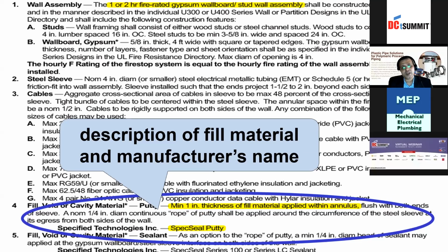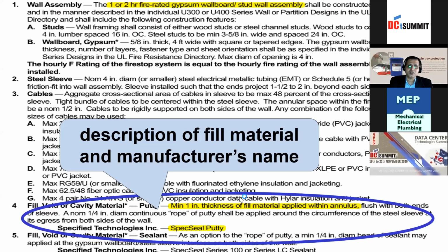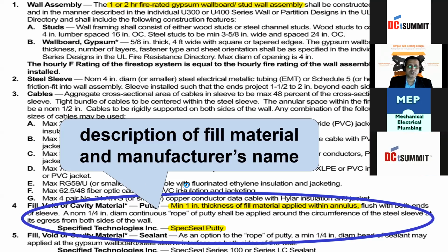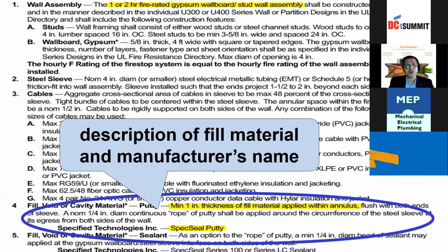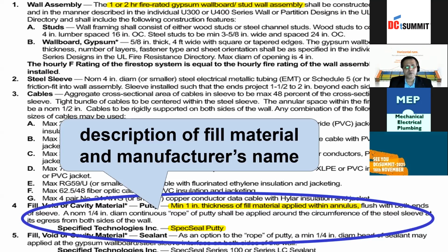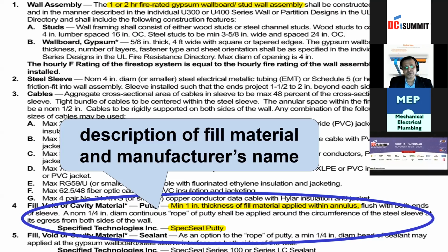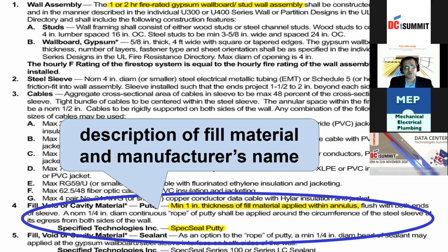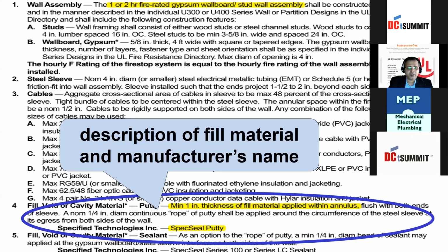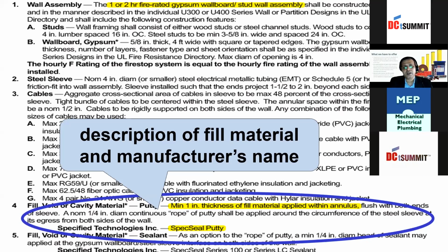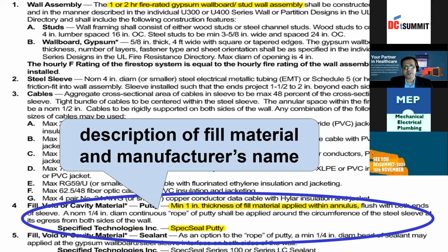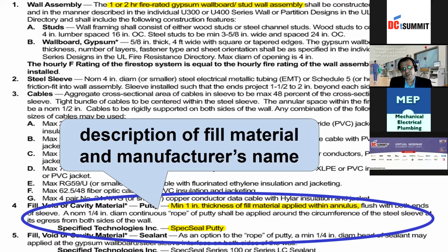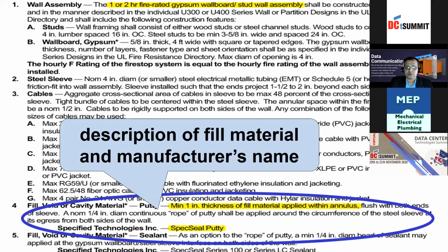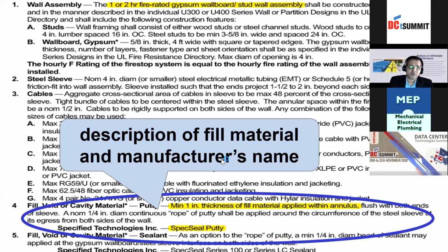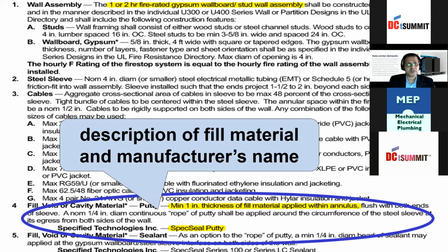But there are scenarios where you have a backing material which has to be 64 kg density rock wool, and then a certain amount of sealant thickness. So this is the most important document which should be asked by any consultant, any installer, to safeguard their building. Even the owners, I would request, they should take up a stand to check on the submittals they get from any of these installers, so that they can compare what standards have been used, whether the complete building has been defined for UL, and whether all certifications are given for each and every scenario. So this is the most important part which any fire stopping company should be giving to the consultants and contractors.